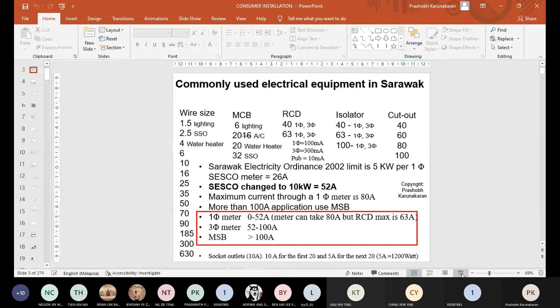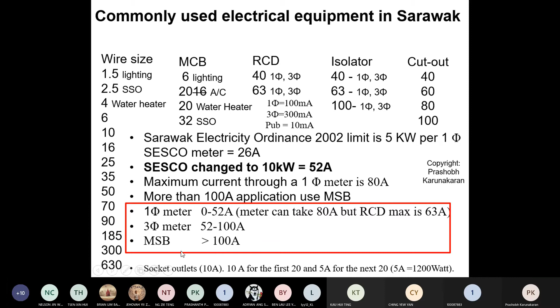So basically, for a single phase meter, which most homes in Kuching use, you can only go up to 52 amps. If you want more than 52 amps, you need to use a three-phase meter, which covers 52 to 100 amps. More than 100 amps, mostly in factories or schools like Swinburne or UCTS, you need a main switchboard. Okay, so that's the spec.